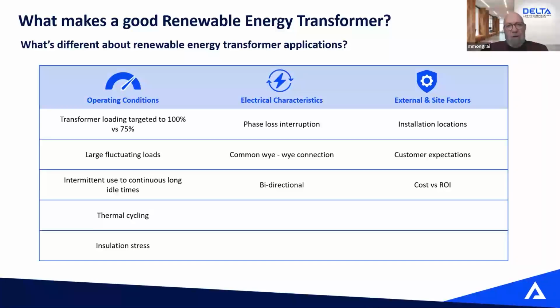If there's more demand for machines or computers, and at night it slows down a little bit, versus a renewable energy transformer, where it depends on your type of source, solar or wind. But usually, if you have a solar farm, for instance, your inverter will output the maximum at noon on a bright sunny day, and at night the output will be zero. So you have these big fluctuations in load over time compared to a standard transformer. Usually, we seek a loading factor of 100% for those renewable transformers. Why? Because since they're not fully loaded all the time, they have their peak depending on the time of day for solar applications, so we might seek a load at 100% during the peak.